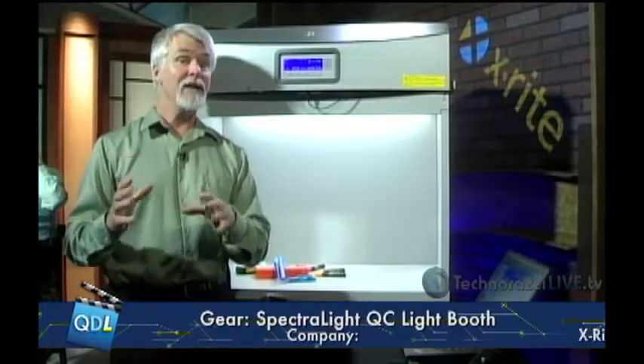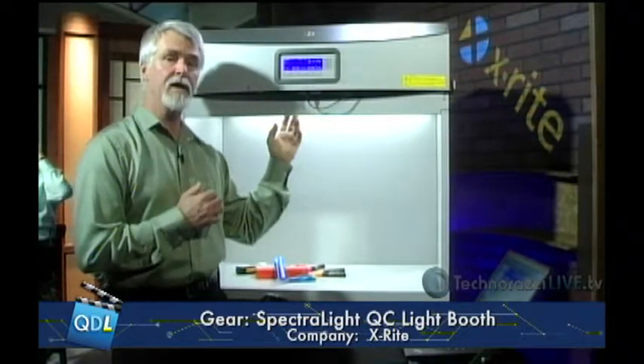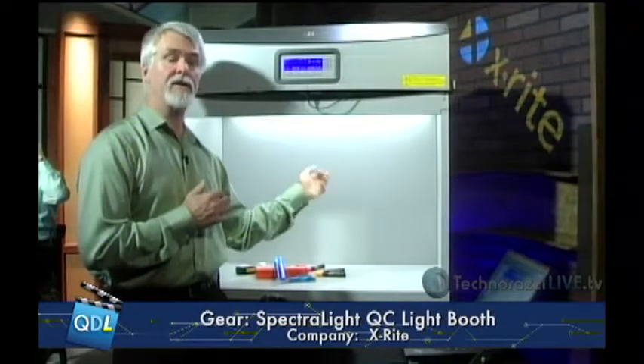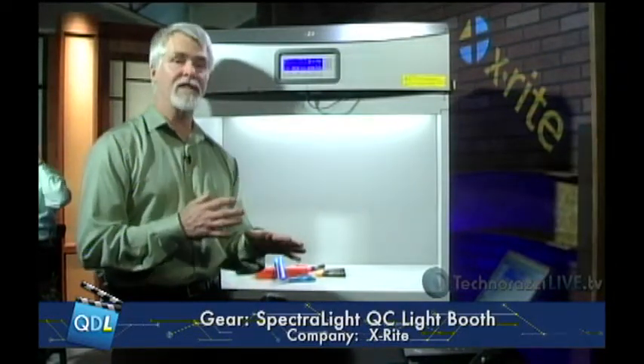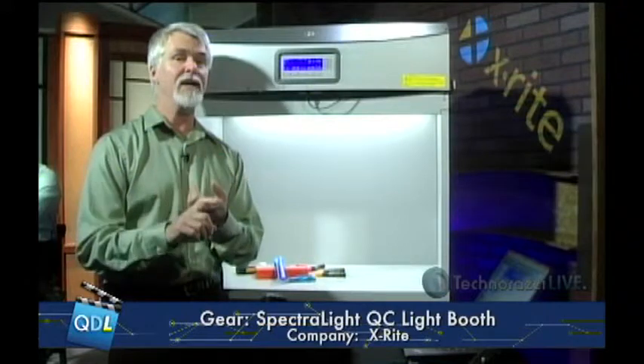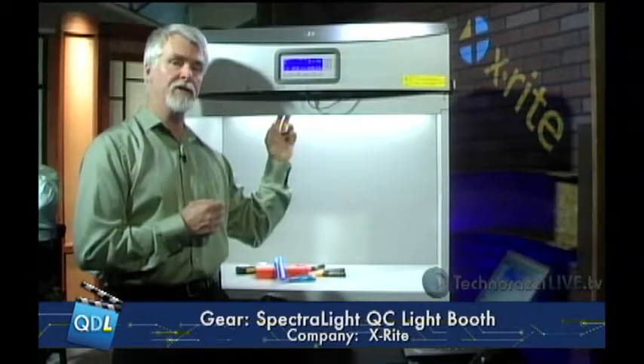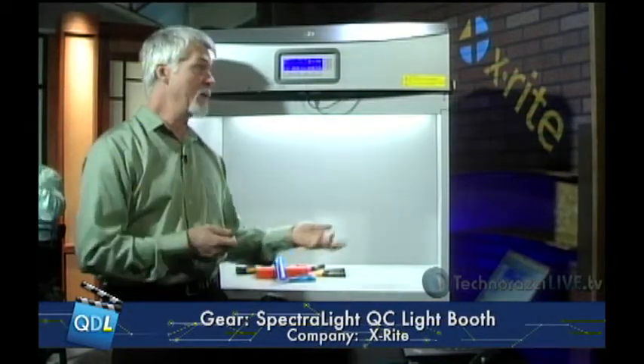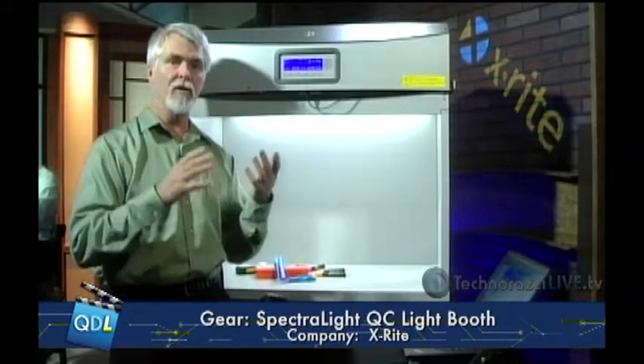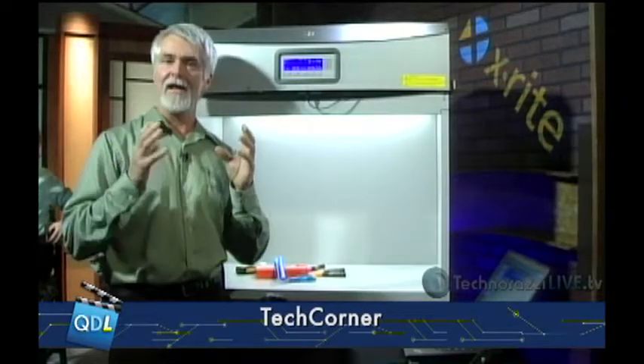This is only useful if you have the same test setup no matter where you go. This is a calibrated light booth — known light intensities, known color temperature, all configured for your specific test. You want your suppliers to be able to do exactly the same test. If you had this booth at your supplier's location, you could download all your settings into a file, send it to them, they'd upload it into their SpectraLight QC, and they'd be able to perform exactly the same test that you're performing. X-Rite suggests that spectrophotometers and color checkers for quantitative checking are important for establishing formulations.